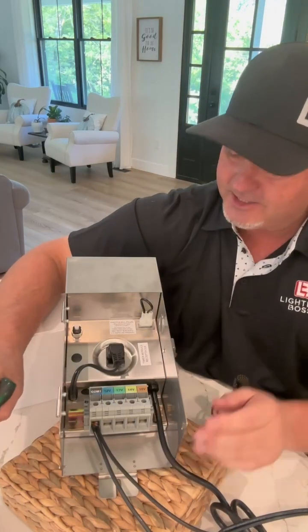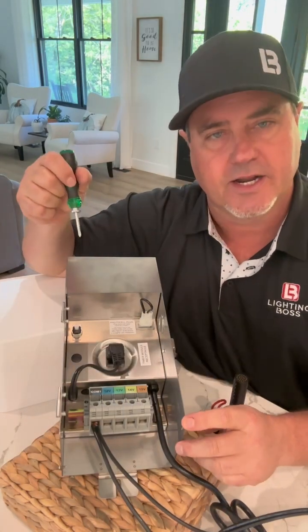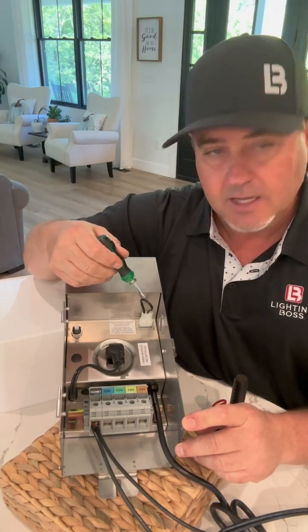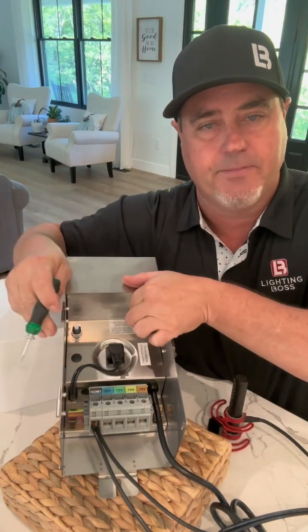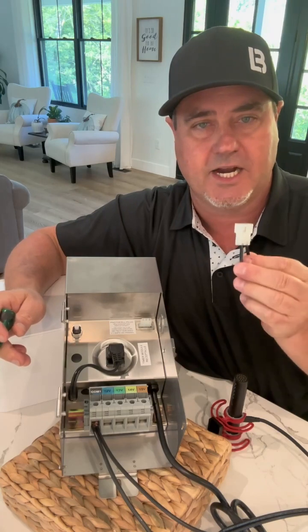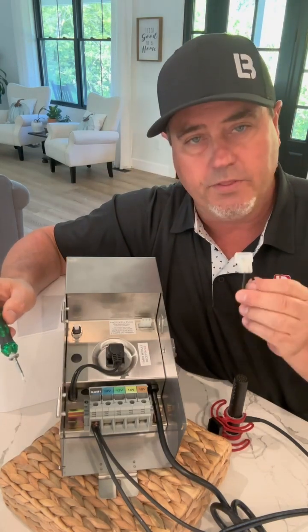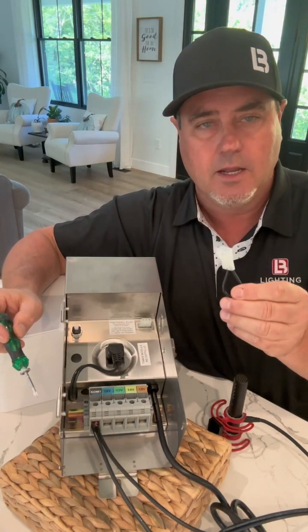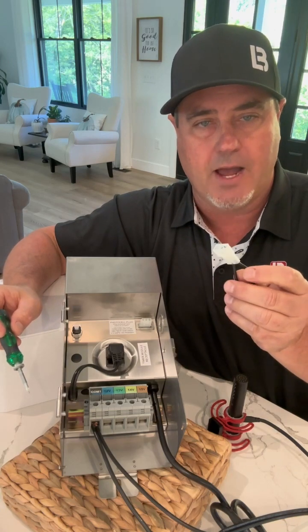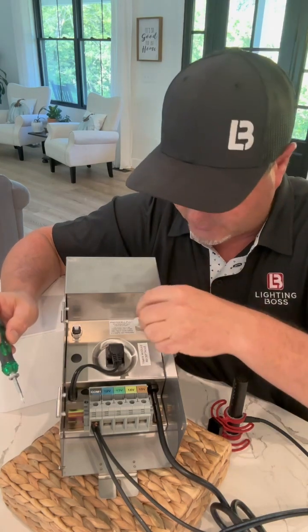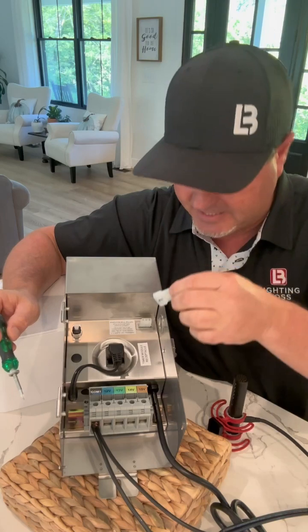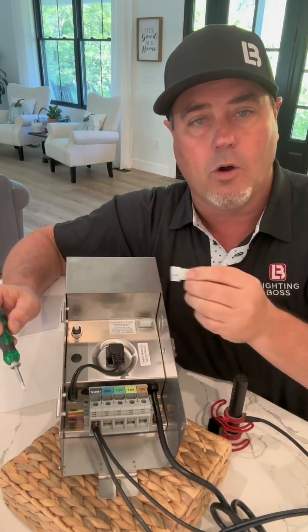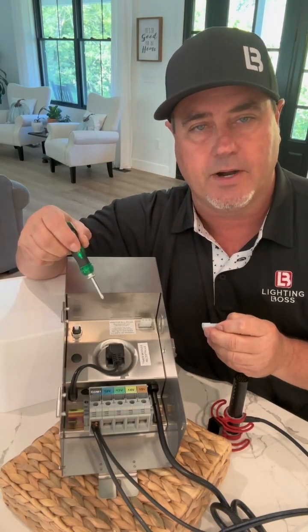All right, so the first thing that you're going to see in here at the top is this loop with an adapter, and here's what it's for. One thing to know is that this is a loop that will complete the circuit for the transformer. So if this is not installed, this transformer will not operate. This will not come on.